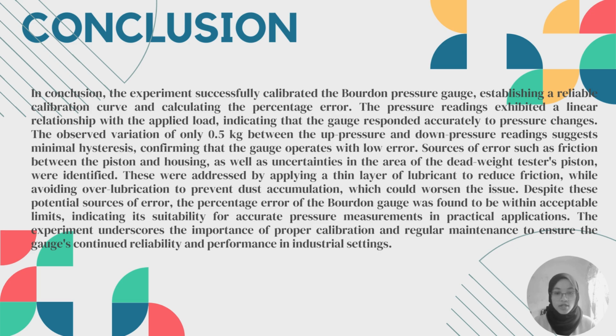For the conclusion, the experiment successfully calibrated the Bourdon pressure gauge, established a reliable calibration curve, and calculated the percentage error. The pressure reading exhibited a linear relationship with applied load, indicating that the gauge responds accurately to pressure change. The observed variation of only 0.5 kg between the up pressure and down pressure readings suggests minimal hysteresis, confirming that the gauge operates with low error.